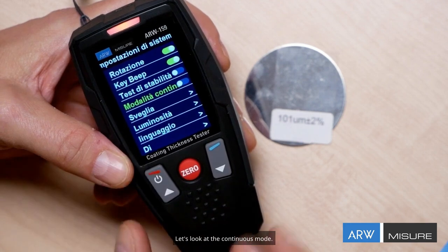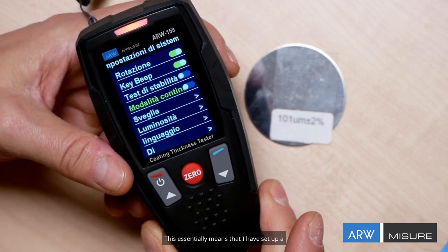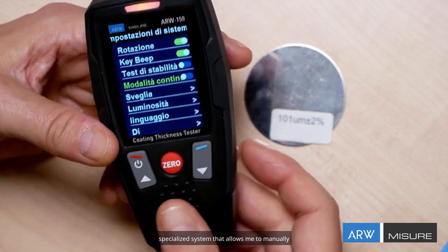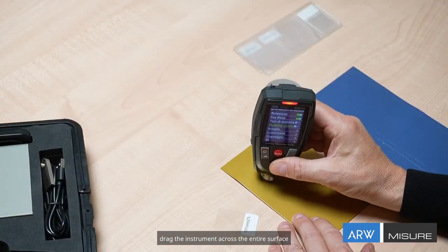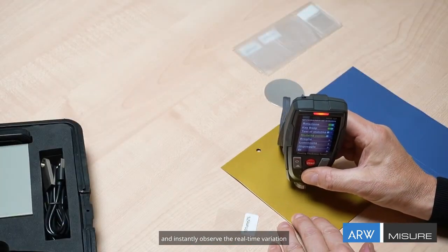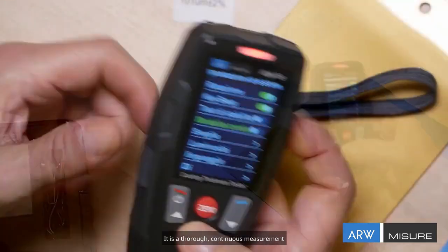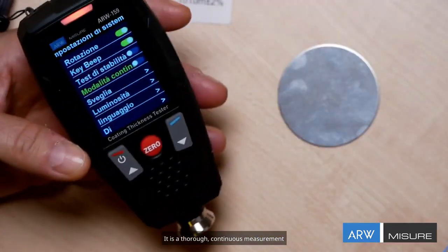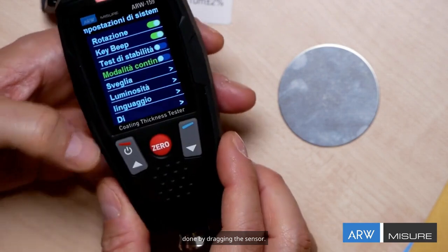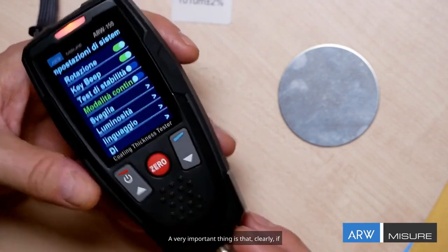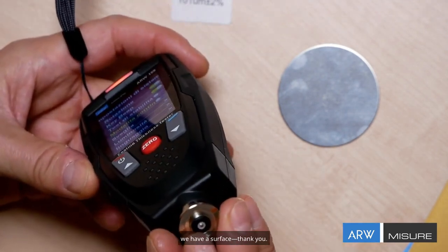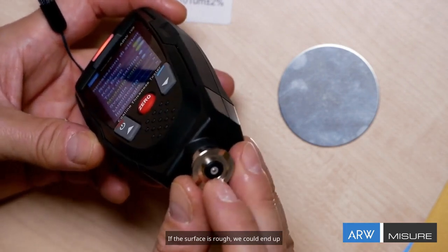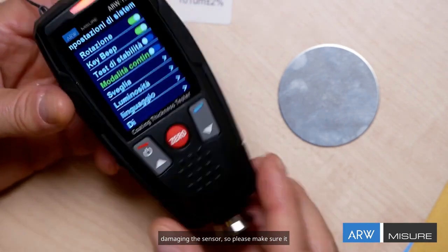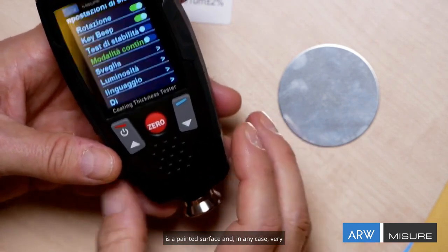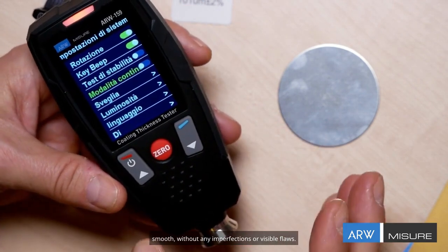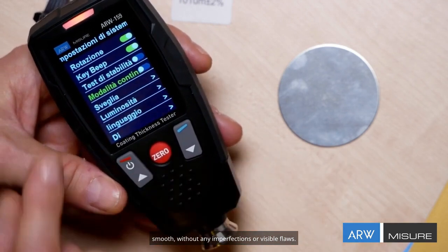Let's look at the continuous mode. This essentially means that I have set up a specialized system that allows me to manually drag the instrument across the entire surface and instantly observe the real-time variation in the data. It is a thorough, continuous measurement process that we could say is effectively done by dragging the sensor. A very important thing is that clearly, if the surface is rough, we could end up damaging the sensor. So please make sure it is a painted surface and in any case, very smooth, without any imperfections or visible flaws.